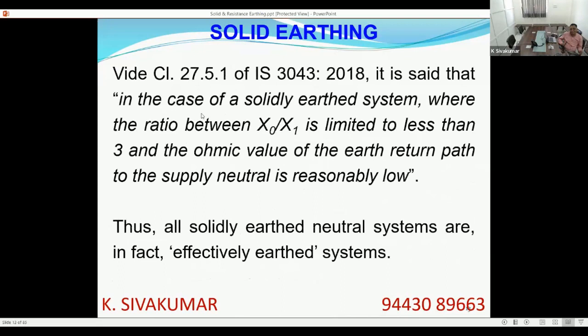But the Indian standard does say, in clause 27.5.1, there is a mention of a solidly earthed system. Whatever qualification is defined for an effectively earthed system in IEEE is satisfied in a solidly earthed system. In this clause, IS 3043 very clearly says, in case of a solidly earthed system, the ratio X0 by X1 is limited to less than 3, and the earth return path is reasonably low. That means it also indirectly says R0 by X1 is less than 1. So going by this, it matches the definition given in IEEE 142, the Green Book.